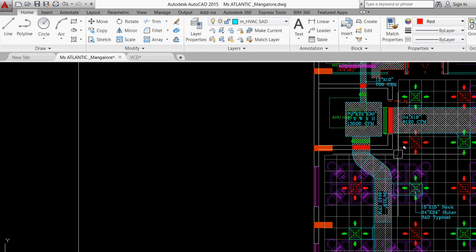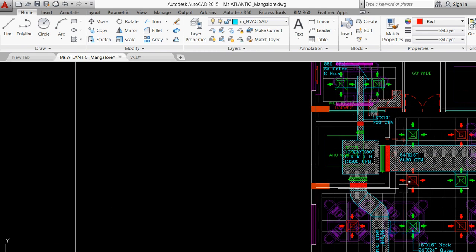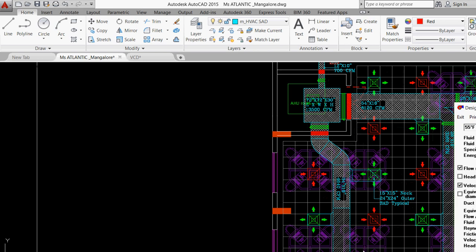So each bar I can make it with 4,500 CFM. So what I'll do here is make it 4,500 CFM, 4,500 CFM, and I'll design it with 500 FPM to 600 FPM. You can also consider 600 in the return air near the AHU. Then I'll change the duct height. Let me assume I would like to utilize that entire space, probably 18 inches or something.